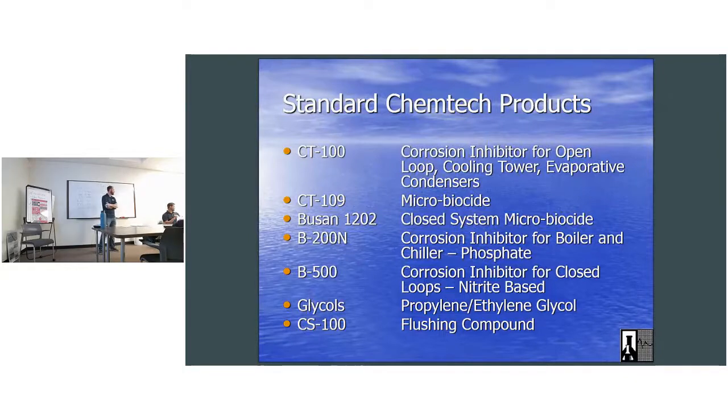And in glycol, really what we're looking for is freeze protection, but there's heat transfer properties with that. You'll see it specifically in MRI chiller machines. You'll see it at 38% ethylene glycol. That's got a heat transfer property, a coefficient they're looking for. If you're doing data facilities, they want 0 glycol because they want to reject as much heat as possible. It gives them the most return. They're trying to get rid of as much heat, and glycol will hold that heat in for a longer period of time, any amount. So most systems, especially where they're not worried about freezing because they have heat all the time, if their systems ever go down, it's just going to be a catastrophic failure. So they'll tie their pumps into their generator systems on most data facilities.